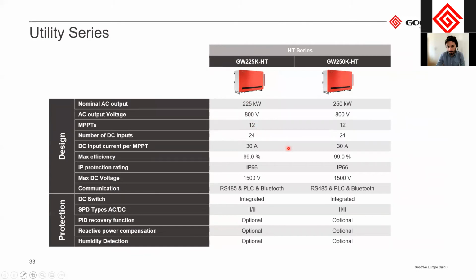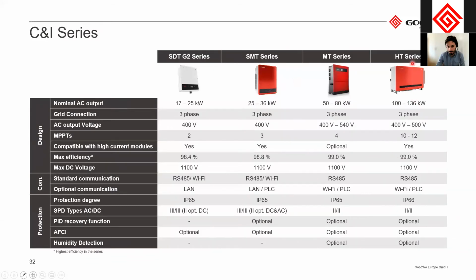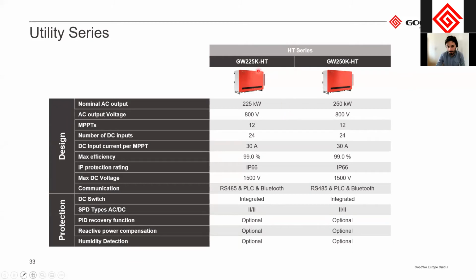If we're looking at our utility scale inverters, you see that they look very similar to the HT series here. They're also called HT, but it's a much higher range. So here you have only two, 225 kilowatt and 250 kilowatt, sorry. The other difference here is that you have a much higher AC output voltage. So here you operate at 800 volt. So in most cases, you will then need a transformer station when using these. The HT series, both for utility scale and C&I, also has a very high input current of 30 amps. And this might also increase in the future to also cope with the coming new modules.